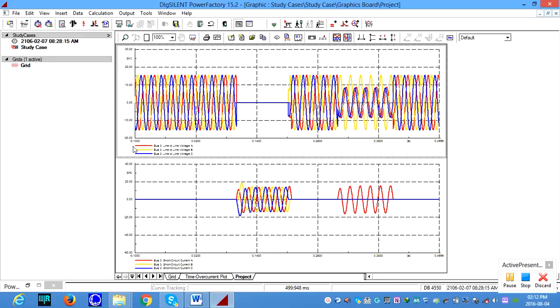So you can look from 0 to 0.1 seconds. There is no fault on the power system, so the system voltage remains stable. At 0.1 seconds, you introduce a three-phase short circuit, the system voltage goes down, and in parallel the fault current is introduced in the system. You can say the fault current is approximately close to 10 kA.